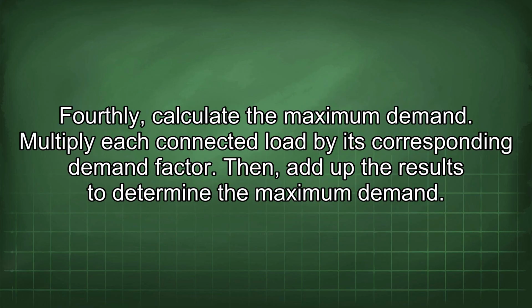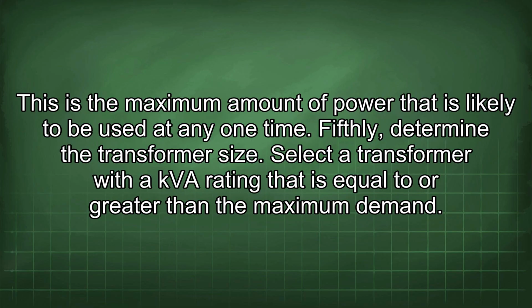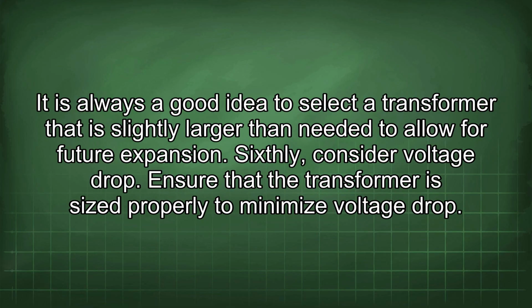Fourthly, calculate the maximum demand. Multiply each connected load by its corresponding demand factor. Then, add up the results to determine the maximum demand. This is the maximum amount of power that is likely to be used at any one time. Fifthly, determine the transformer size. Select a transformer with a kVA rating that is equal to or greater than the maximum demand. It is always a good idea to select a transformer that is slightly larger than needed to allow for future expansion.